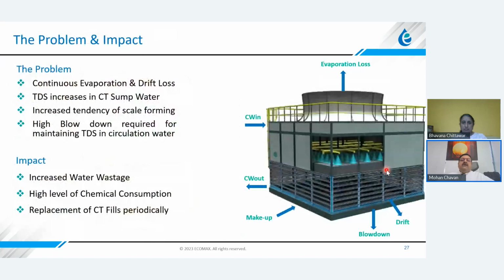The problem with the cooling towers is there is a continuous evaporation happening in the cooling tower, which is a natural process, right? Because we are cooling water from a high temperature to a lower temperature by using the evaporation process. So in that process, there's continuous evaporation happening from the cooling tower. And that's where the TDS of the water in the sump goes up.